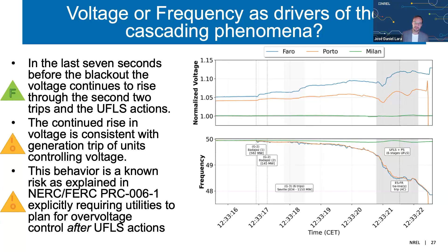But this brings a question about when you operate a system with this high level of penetration of inverter-based sources that don't regulate voltage, that don't regulate reactive power, what should be the interaction between those controls at the plant level, which is regulated to operate at a power factor of 1, and the rest of your system protections?